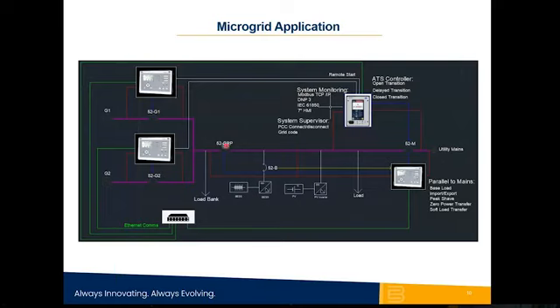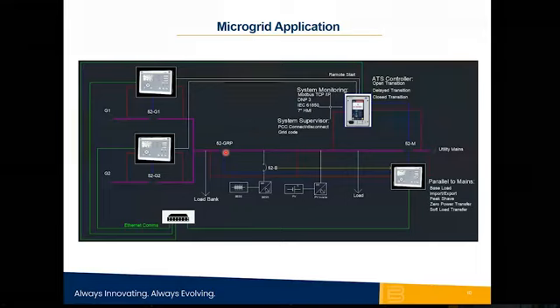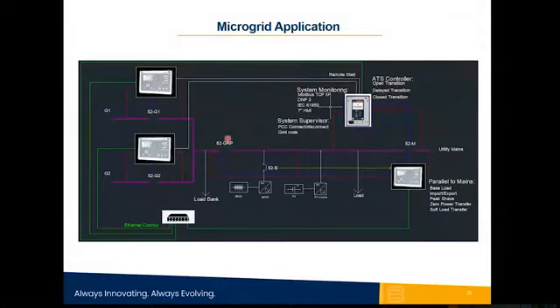So from here, going back in the system, most of us are familiar with this. This is just standard everyday island load share. In our case, it's going to be over Ethernet, which is an advanced form of communications for doing load sharing. And here we have a load bank. So for instance, if you just wanted to load test these generators periodically, once a month, maybe for NFPA 110 purposes, then the load bank here gives you the flexibility to do that.